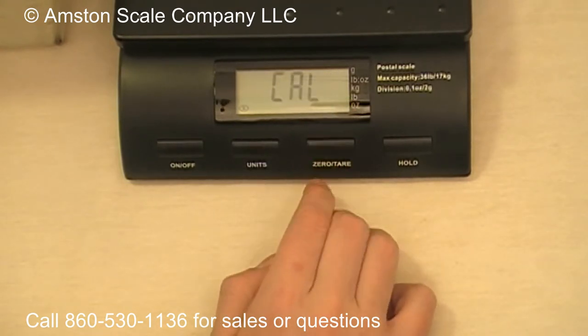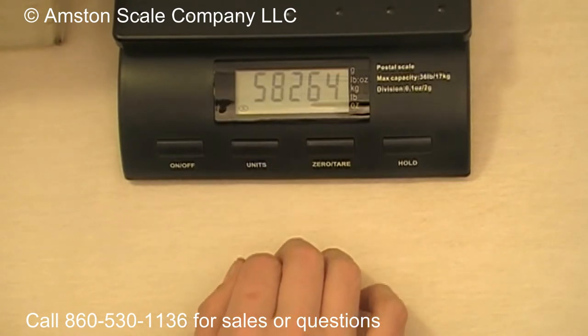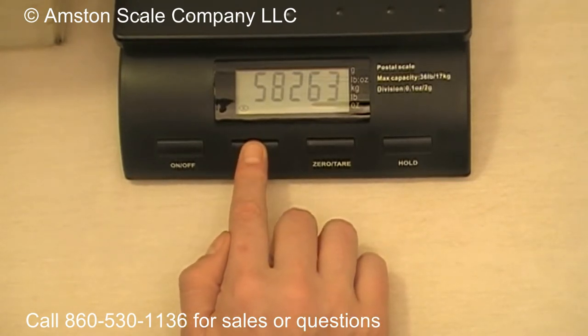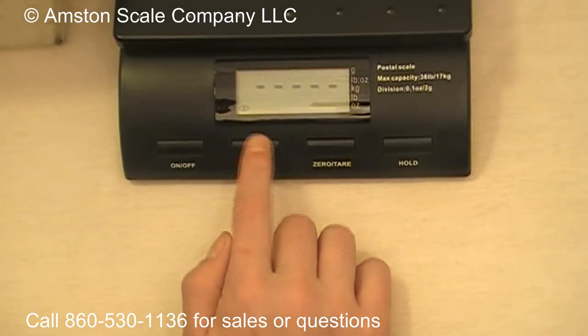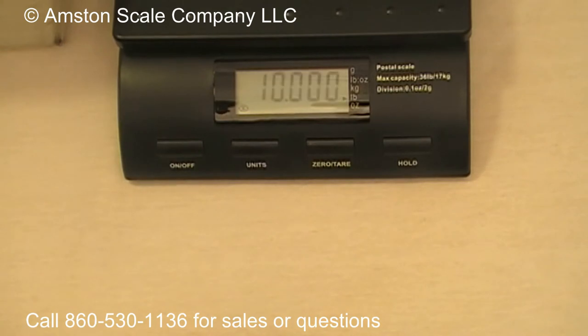you want to press the zero tare key, and that's going to show Cal. Then it's going to show the AD value, and then you want to press the Unit button for a second. You'll see that series of lines, and now it's flashing 10 and it's ready for the calibration weight.